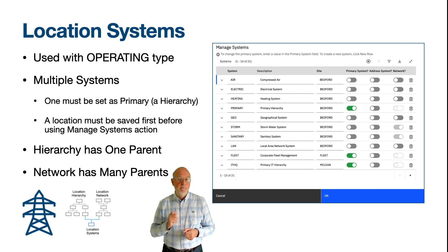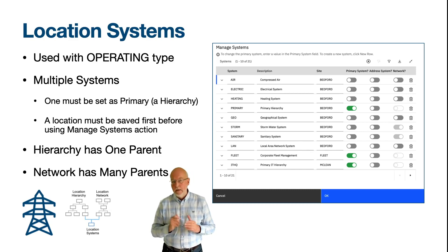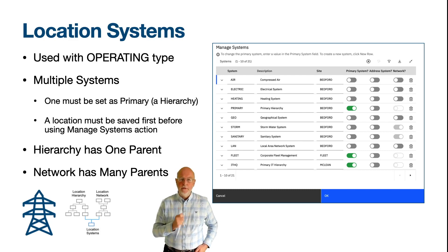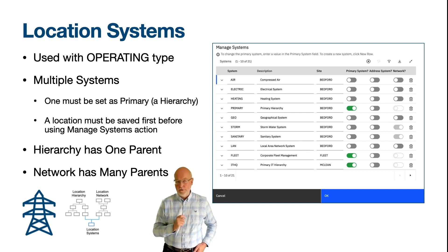An operating location can belong to multiple systems, either hierarchical or network. A location system is a means of grouping locations that share a common purpose. The primary system is often geographic-based and supports drill-down — it is what is needed to help find the assets that exist at those operating locations. The most frequent use of a secondary system is to group locations according to the system they support, for example heating and ventilation, water, power, or drainage.